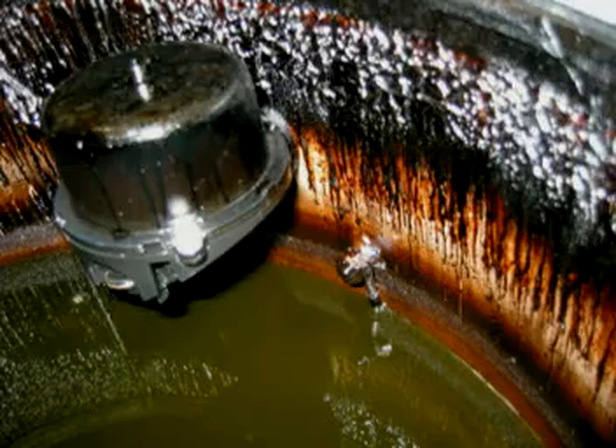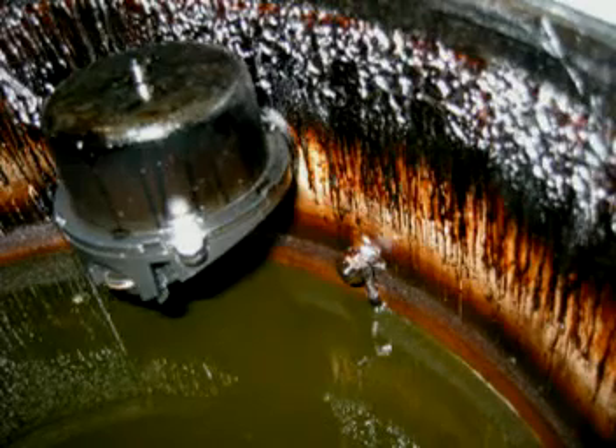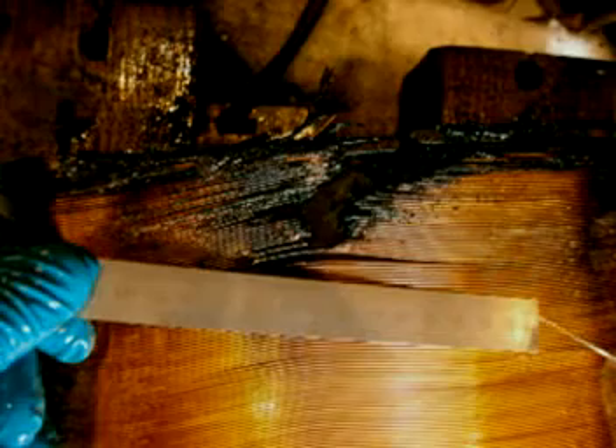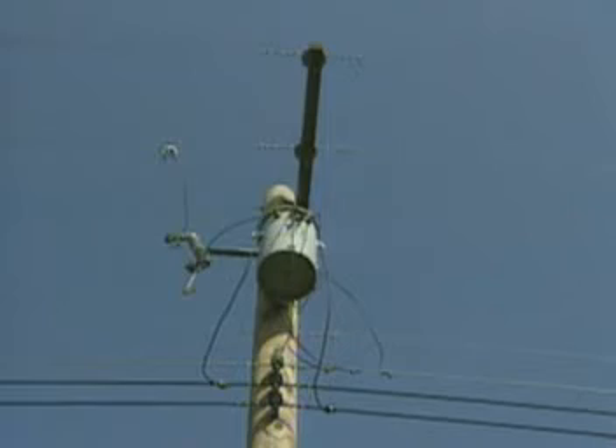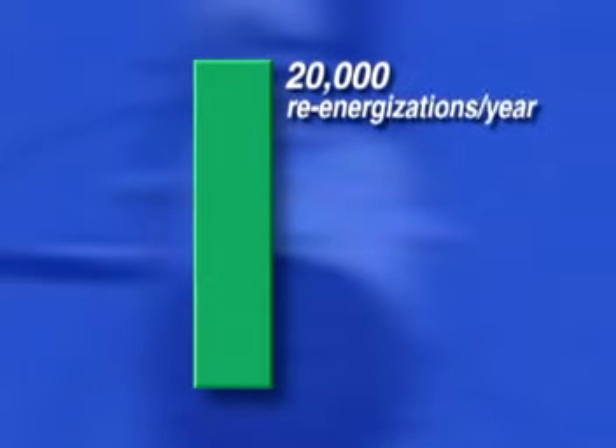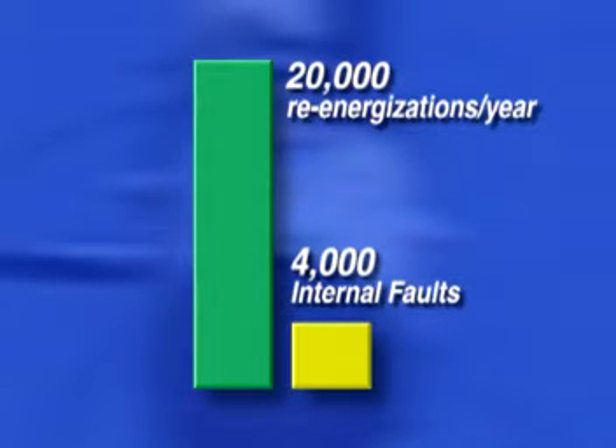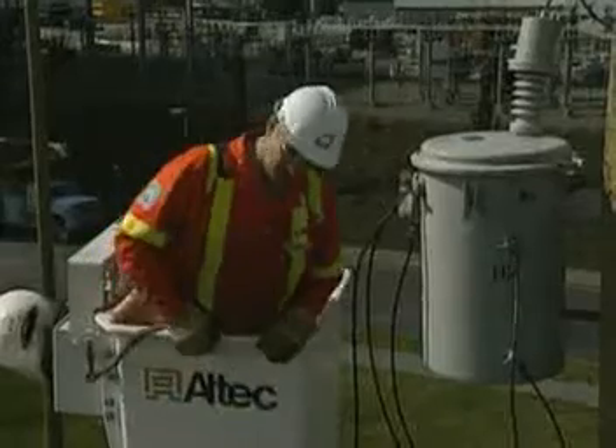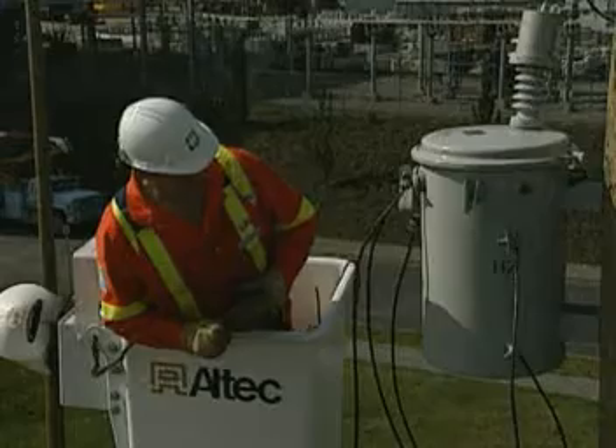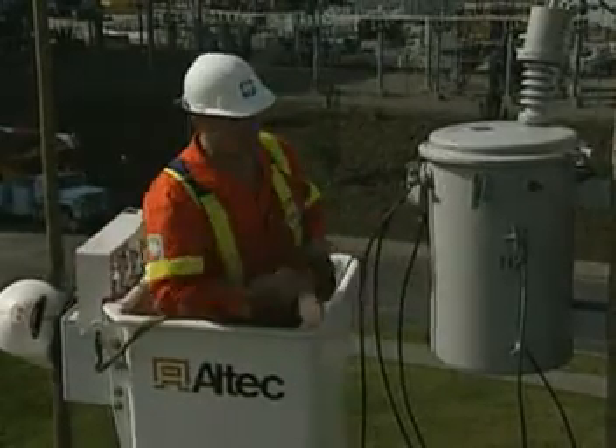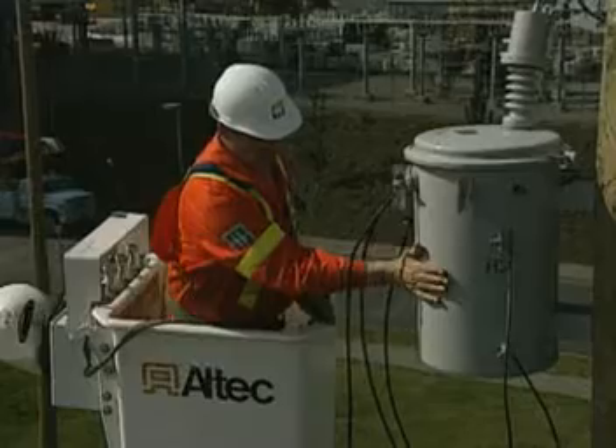To give you an idea of how often transformers fault, let's look at the reports from a large North American utility. This utility was selected because of the area's diverse weather conditions, providing a representative sample of the industry in general. This utility documented that it did over 20,000 transformer re-energization operations in 1 year. Of these, it was calculated that 4,000 operations involved transformers with some sort of internal fault where the transformer was replaced. The line crews spent a significant amount of time trying to determine the problem with each transformer, translating to many hours of service outages.